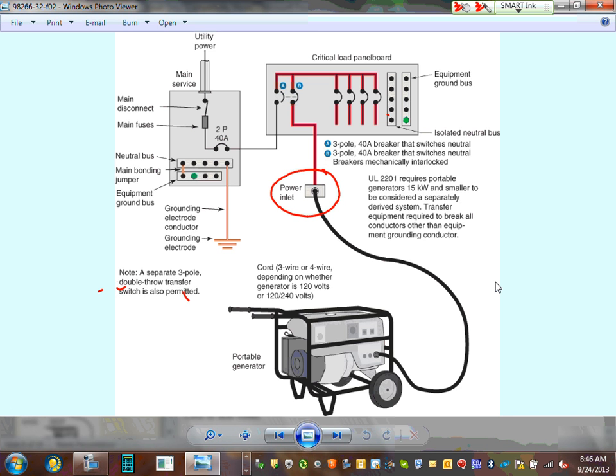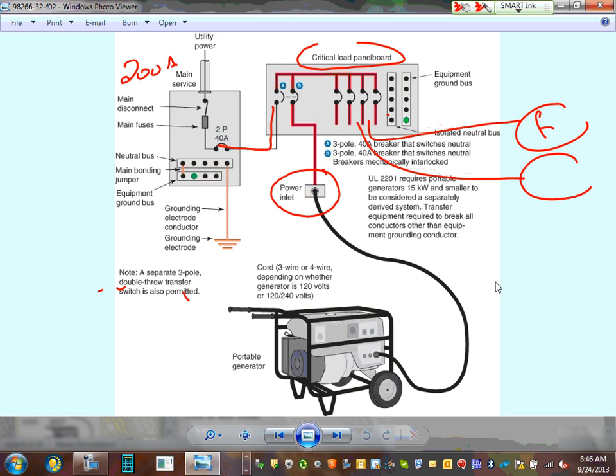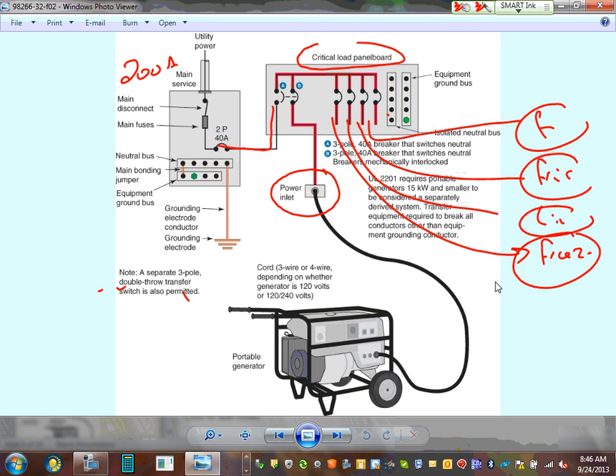So what you do is you take your main panel, there's your 200 amp panel. You take a 40 amp feed, can you guys see the 40 amp feed coming from here to a separate panel called a critical panel? And then from here, you feed your furnace and your fridge and some lights. For example, let's just say you have light, fridge, freezer. So here's four circuits. You decide on these four circuits, not four devices, four circuits. So you can have five lights here, and for the refrigerator you can have multiple things if you want, a couple of extra receptacles.